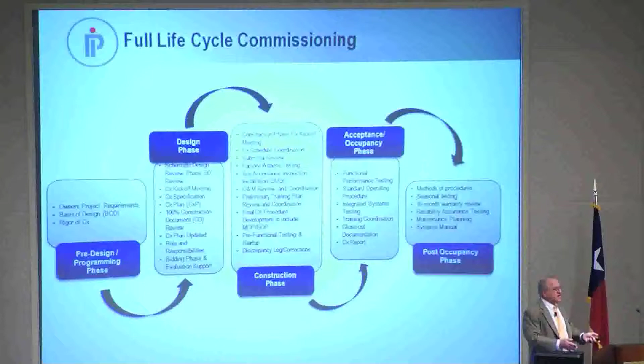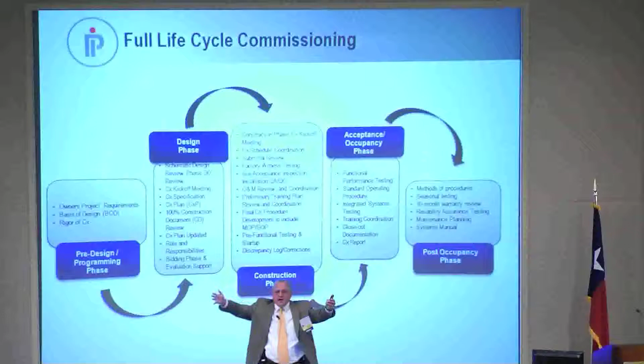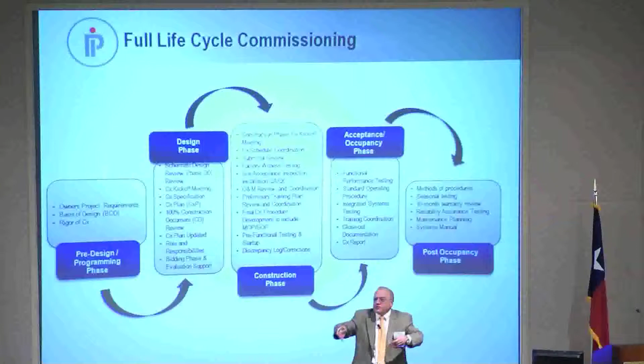You certainly don't want to train your operators to do that while carrying live load - there's significant risk. You'd find the same issue with an N+2 generator system if one generator is down, making you N+1, and you have a utility failure. Do you want to start training your maintenance staff on how to handle that during an actual utility failure? So I want to stress that these procedures should be developed early - even a starter kit covering 10 electrical, 10 mechanical scenarios, some controls, and some failure scenarios - that you can turn over during the transitional period.